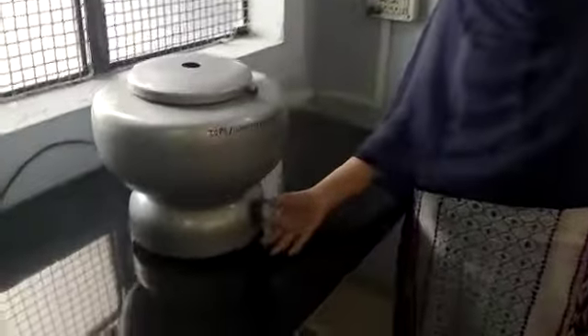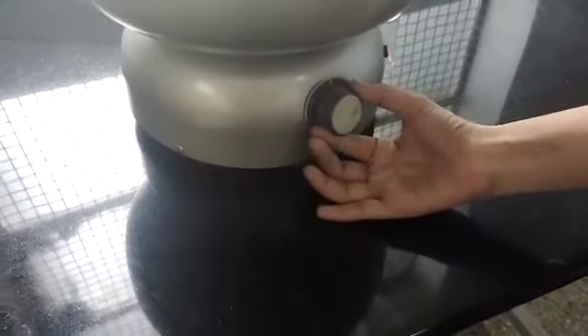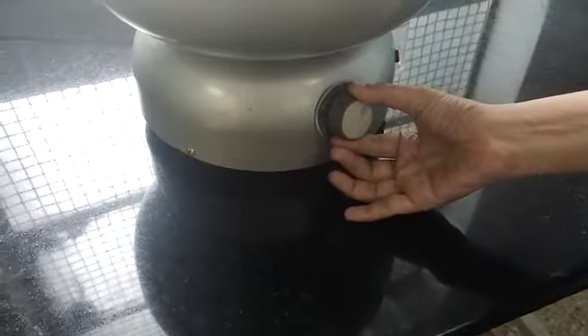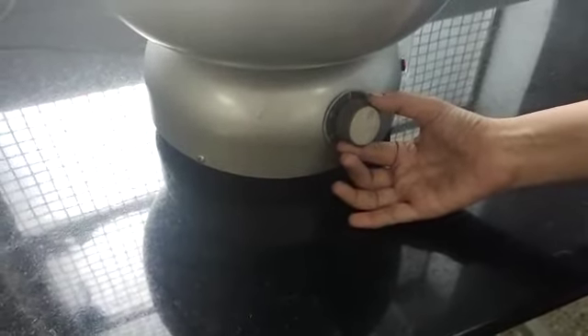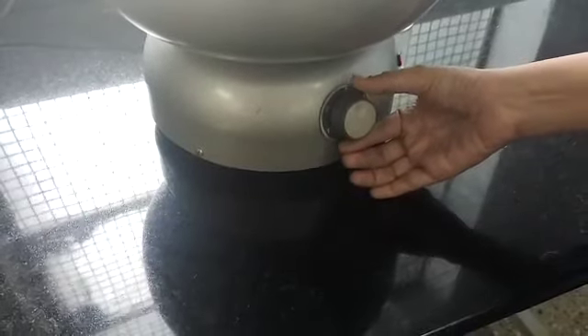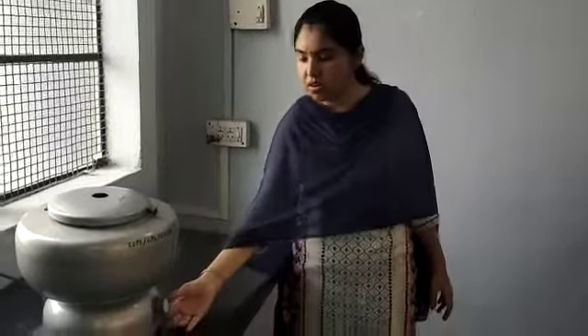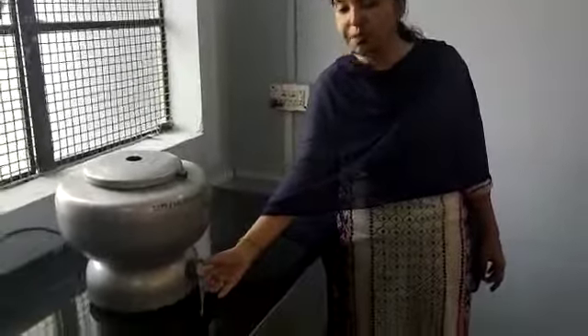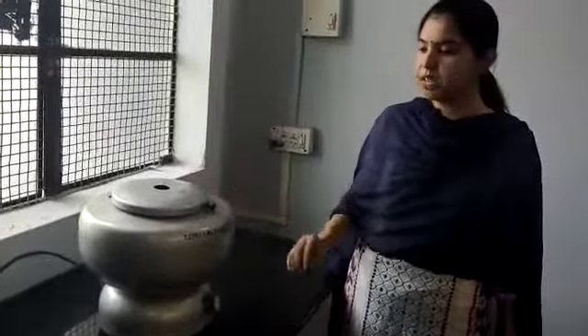So before we switch off the centrifuge instrument, you have to first minimize the speed from 2100 to 1400, then bring it to the further minimum speed of 700 and then put it to 0, that is, switch off the instrument. So you have to slowly minimize the speed. Do not directly switch off the centrifuge. This may damage the instrument. So these are some points that you need to keep in mind while switching off the instrument. Also, once the centrifuge cycle is completed, switch off the main switch. Let it rest for some time and then open the lid.